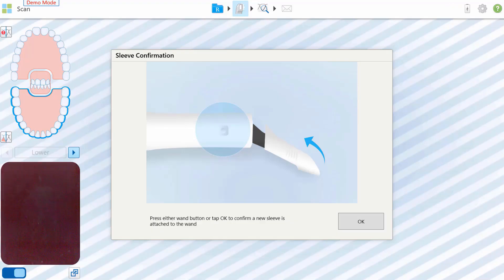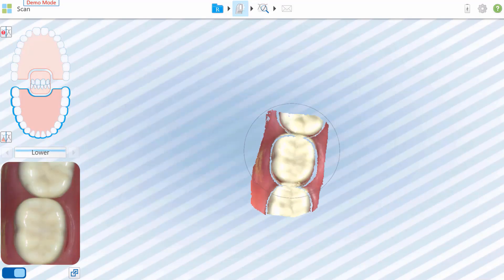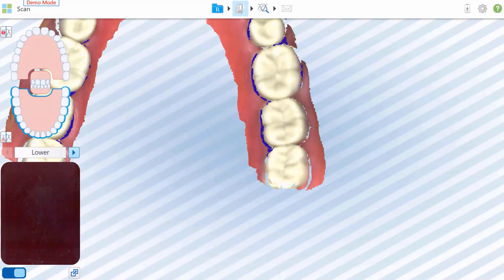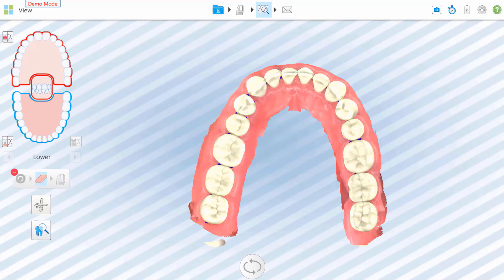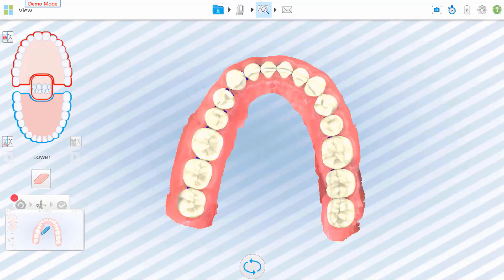they are in demo mode and to exit before scanning actual patients. Practice using all scan mode features such as selection, and disable/enable AI cleanup. In view mode, practice using features such as the eraser tool and snapshot tool.